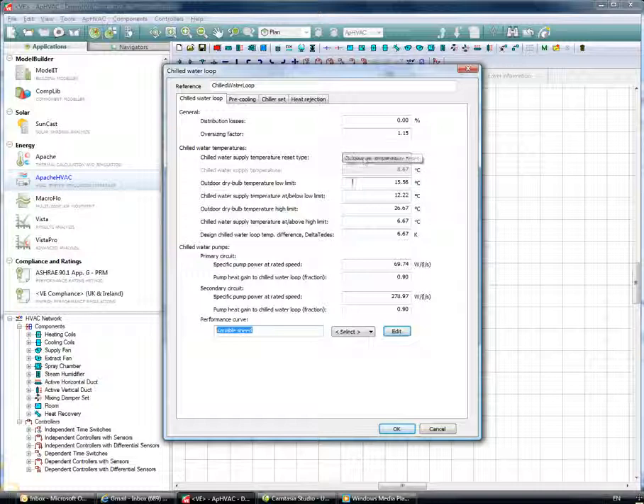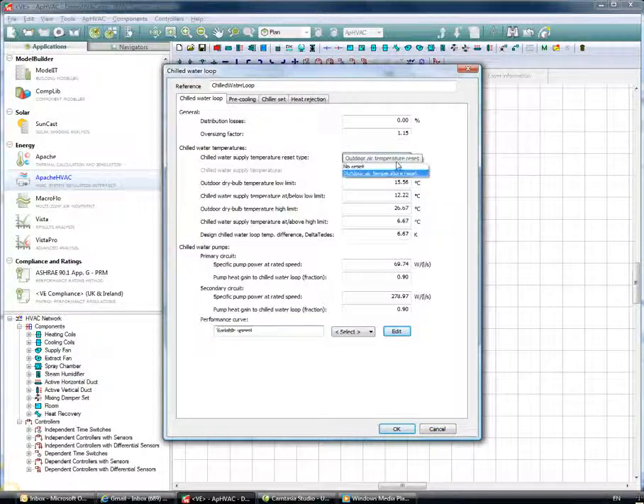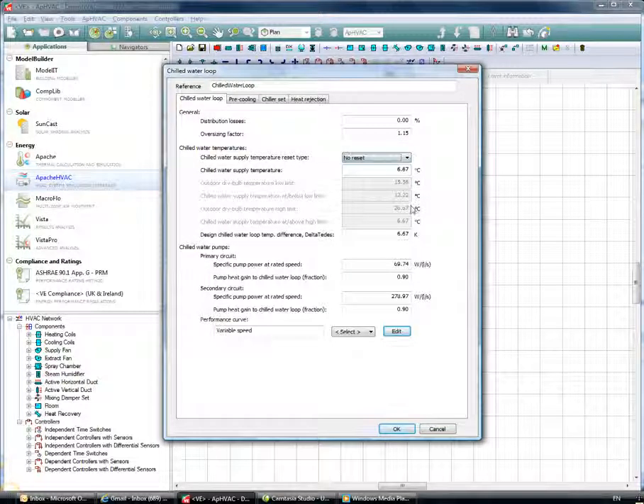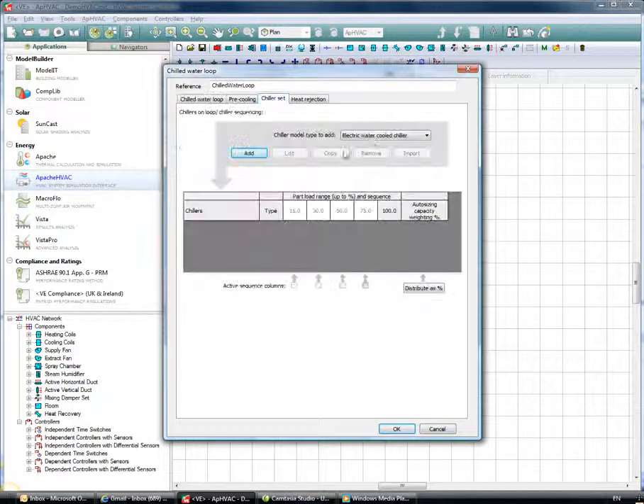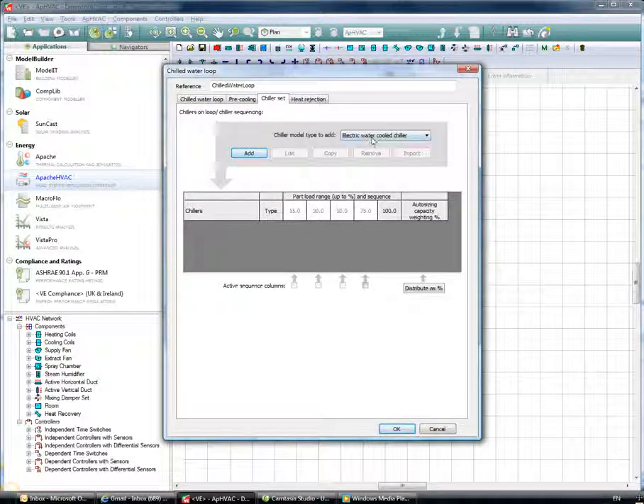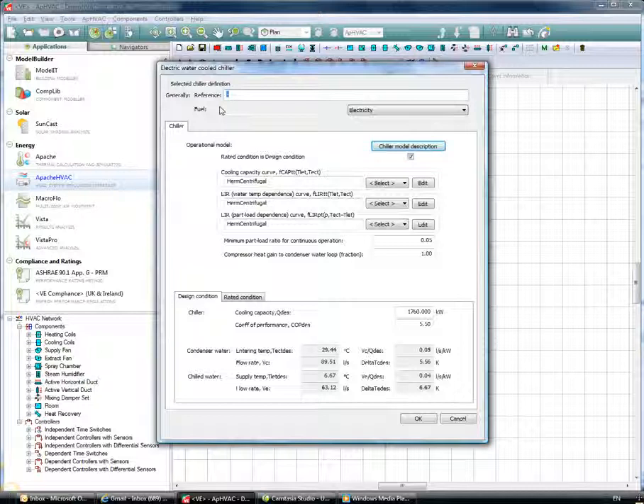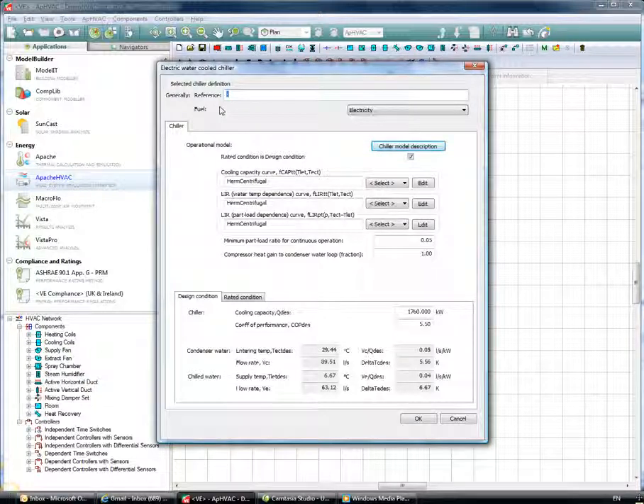We'll change to a variable speed pump as we've done. For the chilled water supply temperature, we can change it from a reset based on outside air temperature to no reset. Going into the Chiller Set, I'll select the electric water-cooled chiller.